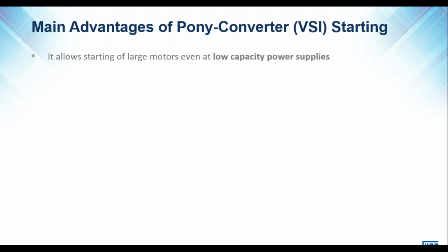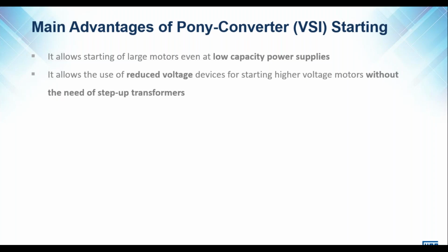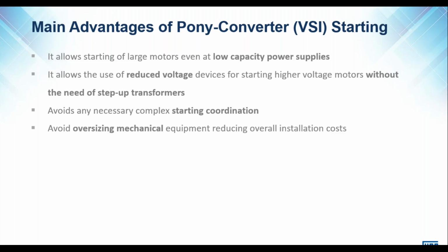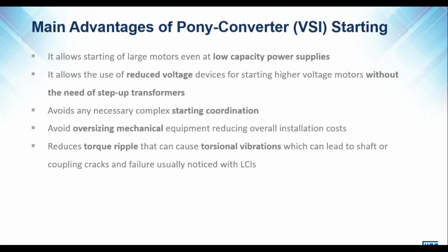Okay. Some of the advantages of this kind of starting method: we're essentially using the VSD to start the motor with a very, very low impact on the power supply. It also allows the use of reduced voltage devices, and from a CapEx point of view, that is the main consideration there. It avoids complex starting coordination, avoids oversizing mechanical equipment, reducing installation costs, and reduces torque ripple that can cause torsional vibrations. Why? Because we can set the acceleration time in the VSD, and we can ramp up the motor very slowly if we need to.